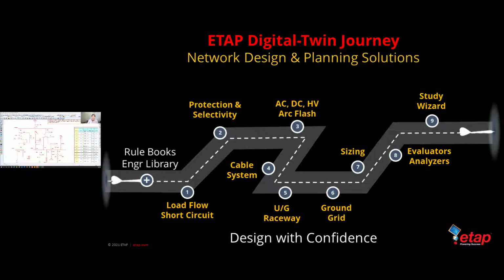I can select the entire project and run an auto evaluation. So now I am running a short circuit at every bus in the system, and I'm evaluating how well I did for protection and coordination. On the general tab, I see a summary of how well I've done for all of the devices. But I can go to one in particular here. I click Transformer 2. You see the protection curve on the side. The TCC study is automatically updated to the TCC study that's protecting Transformer T3 in this case. The one line changes accordingly to the appropriate location and highlights that device for you.